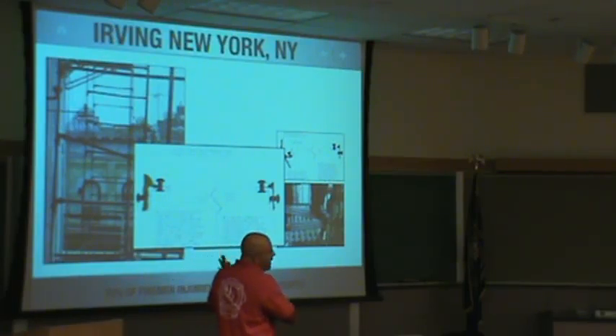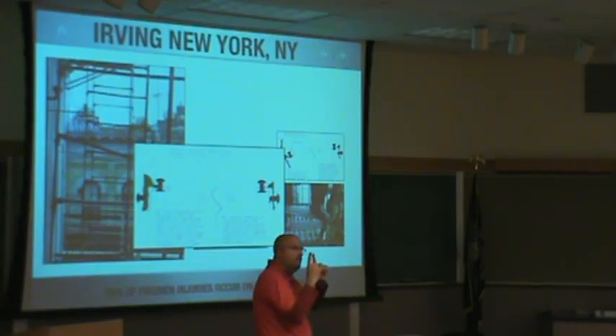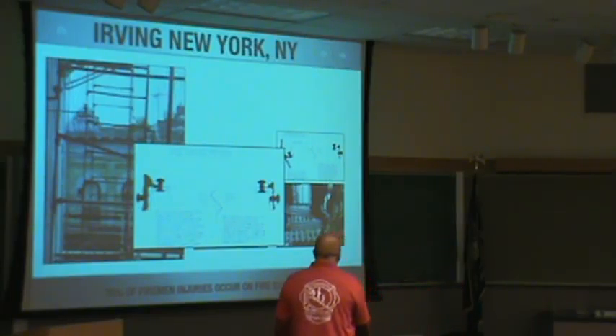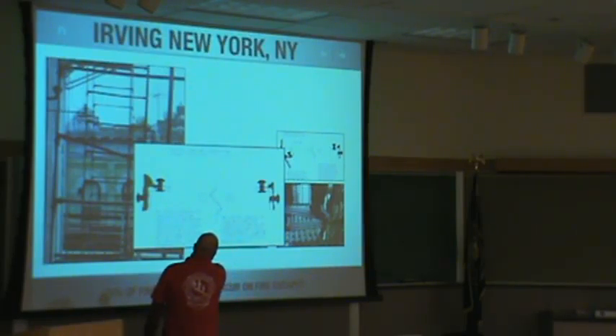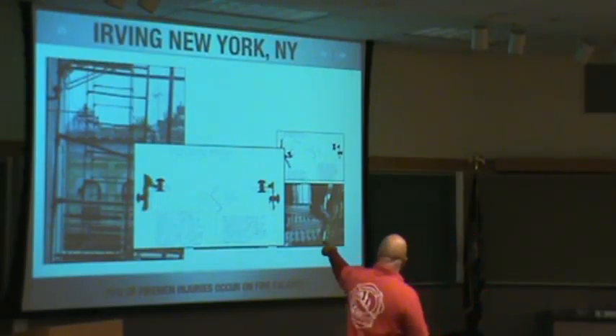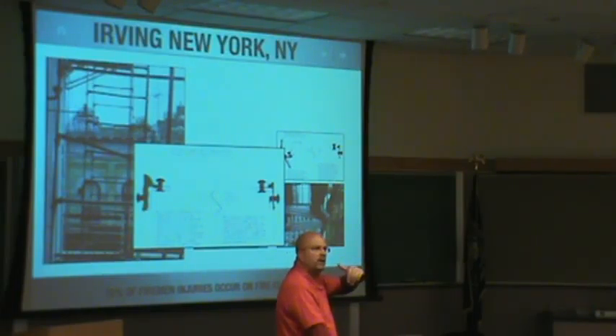Now we're 50 to 75 years later, which is today. There's a quarter inch of rust in there, and that rivet is only so long — only 3/8ths long — and you've already pushed it away from itself a quarter inch or more. So you're dangling. All this piece of angle needs is to hit a little bit of that rivet, but it's already been pushed out. That's why — do you care about what bolt you use, whether it's stainless or a rated bolt? No. What kills a bolt is the fact that the iron is eaten, and as soon as you push it away from the bolt shaft, the thread wants to pass through. That's your problem — not the bolt.